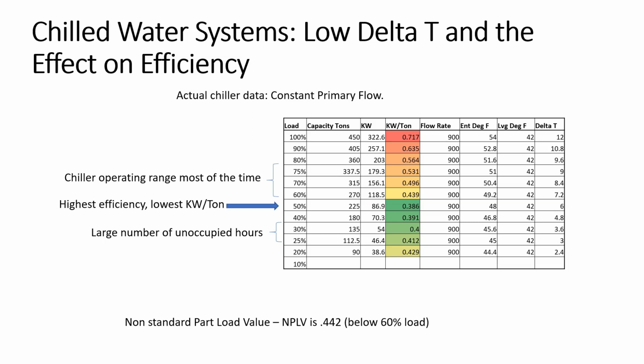Right. Now, I thought, and I guess I was totally mistaken here, I thought that the whole idea of low delta T has to do with chill water flow. Well, in this case, that's the issue. This is constant primary. They have a constant flow on this chiller all the time. Exactly. So if you have a low delta T, then you want to decrease the chill water flow so you can have a higher delta T, and then the chiller will run more efficiently. Yes, and so that would push this efficiency closer to more efficient operation with a higher delta T by lowering the flow. And this machine will do it. It's just that they didn't do it.